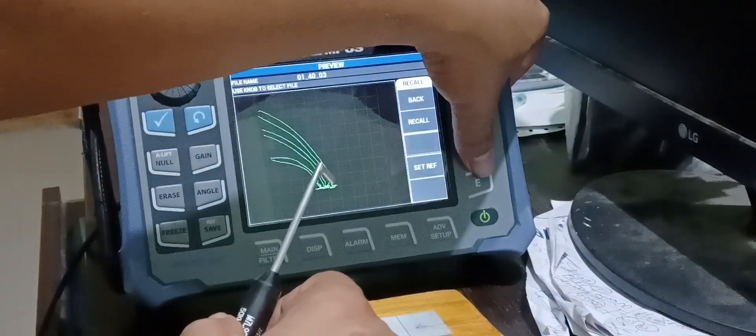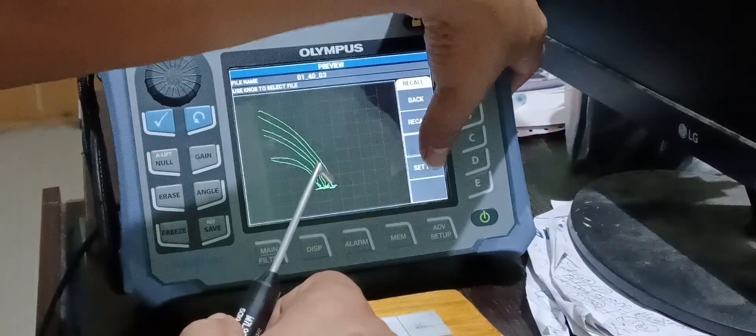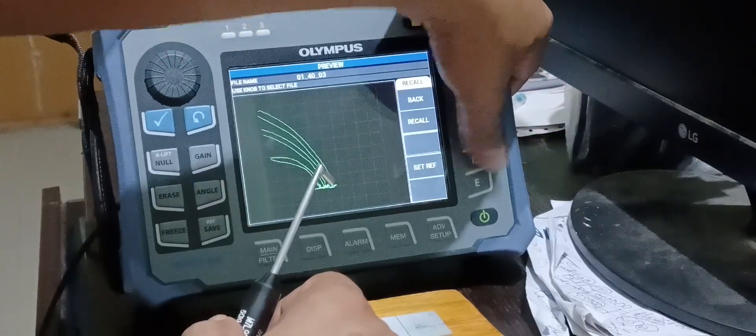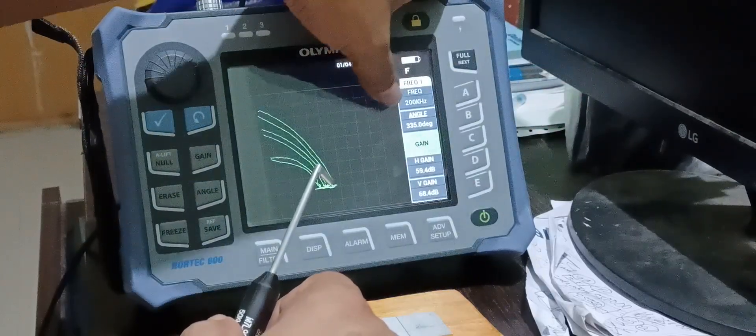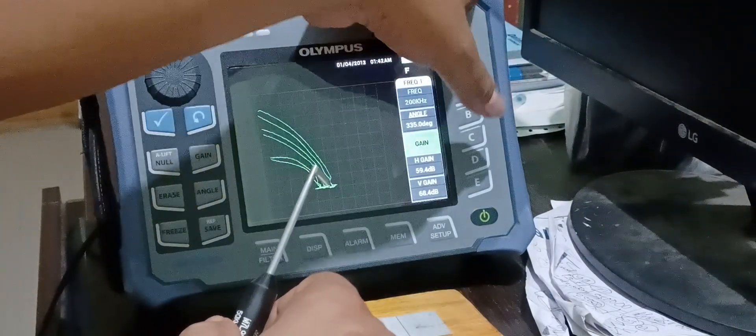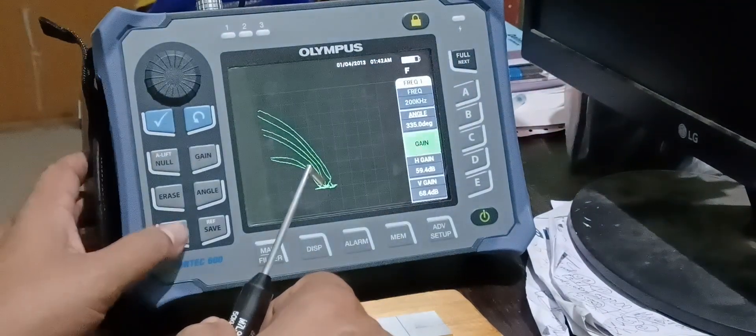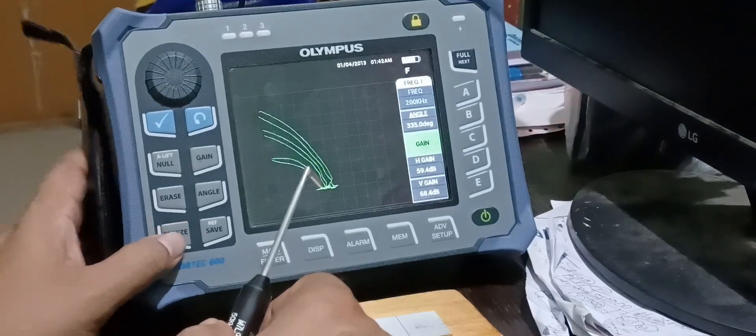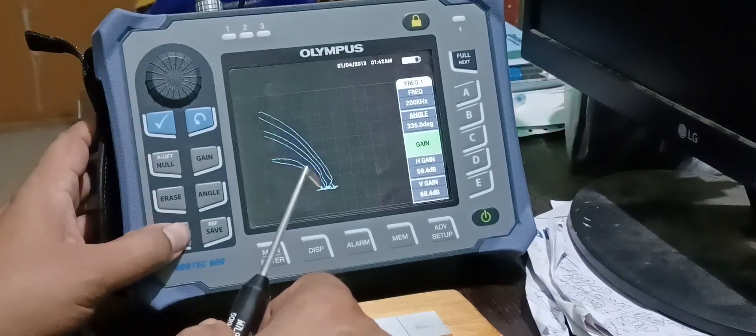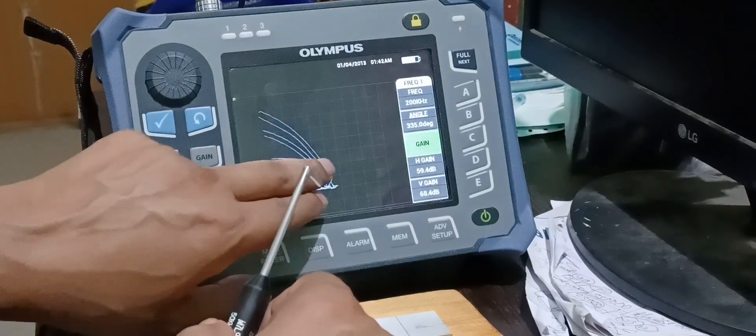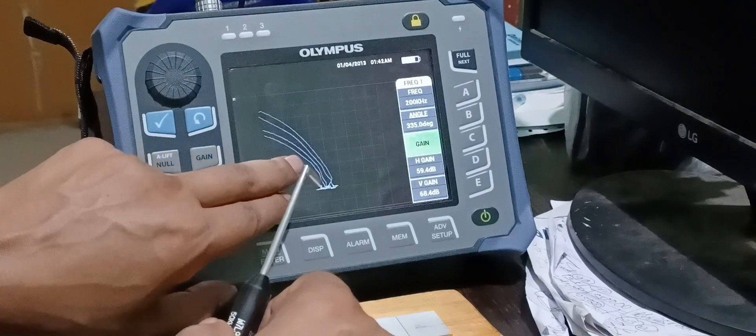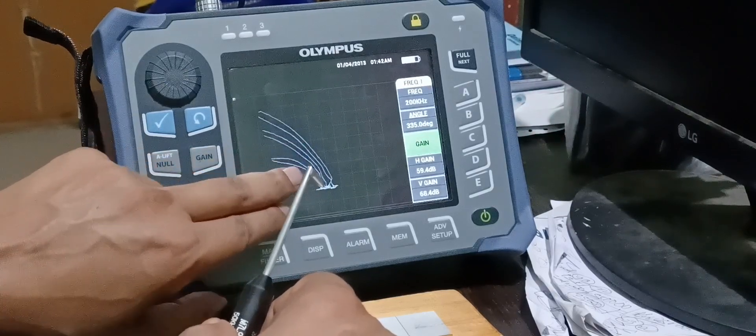Now, I have to set reference. Just put it in the set reference menu. D over here. Now, it is set reference. Set reference or unfreeze. That is set reference. All button is pressed. Now, we just unfreeze this signal. Now, the curve is, these three graphs are already been set as referenced. Referenced graph for these three signals, for these three crack signals.